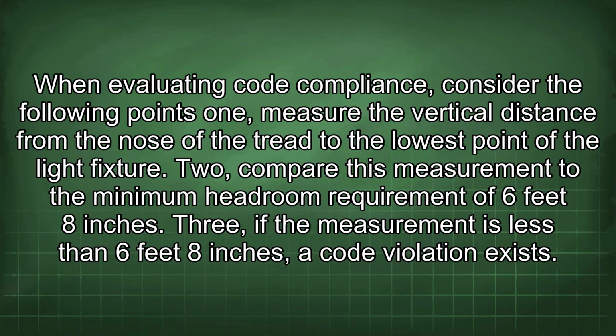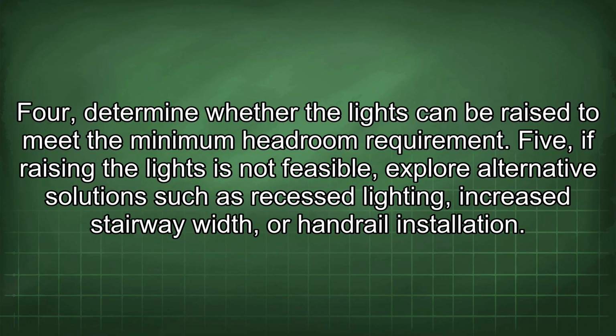1. Measure the vertical distance from the nose of the tread to the lowest point of the light fixture. 2. Compare this measurement to the minimum headroom requirement of 6 feet 8 inches. 3. If the measurement is less than 6 feet 8 inches, a code violation exists. 4. Determine whether the lights can be raised to meet the minimum headroom requirement. 5. If raising the lights is not feasible, explore alternative solutions such as recessed lighting, increased stairway width, or handrail installation.